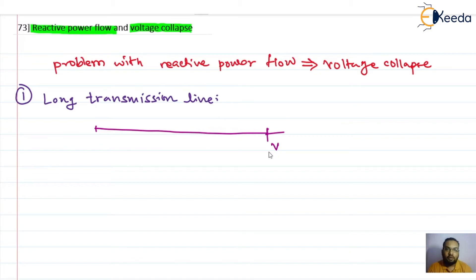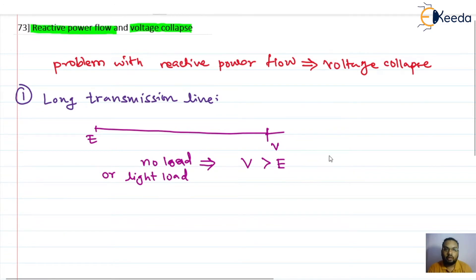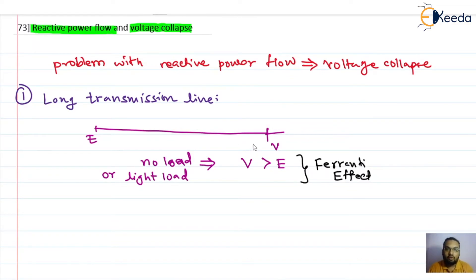This problem is different for different loading conditions. Under no load condition, the receiving end voltage becomes greater than the sending end voltage for the long transmission line. This situation can also occur under light load condition, and this phenomenon is popularly known as the Ferranti effect. The better way is to provide compensation for the transmission line to avoid this Ferranti effect.